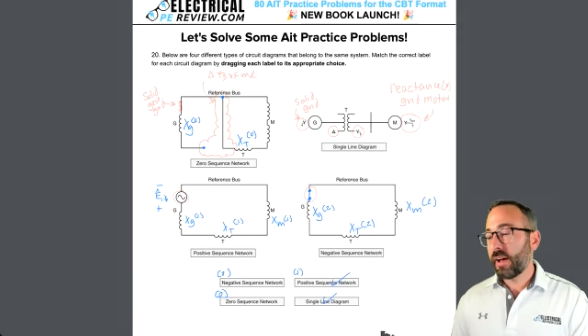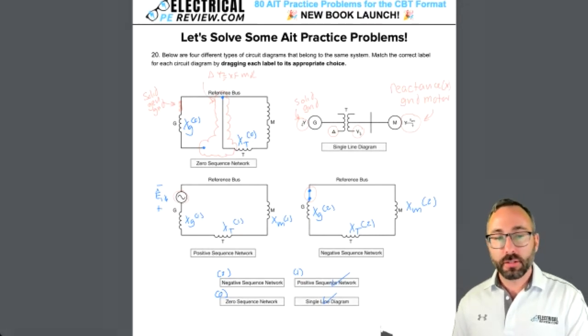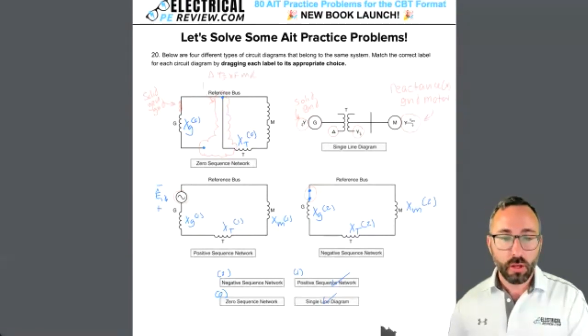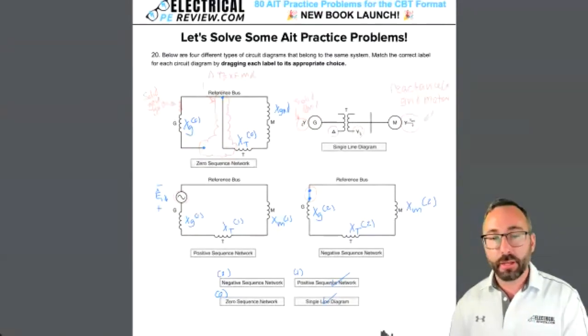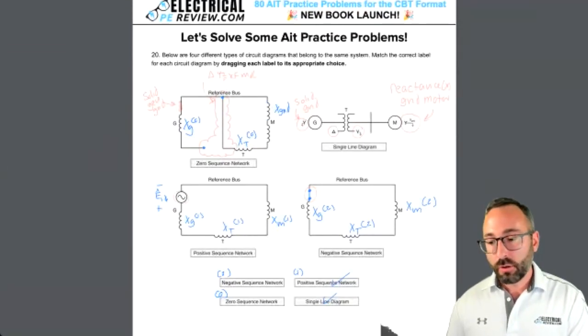What happens if I have a ground impedance or a ground reactance? What happens on the zero sequence network? I'm going to take that value X ground, whatever the reactance is right here, but I have to multiply it by something before I stick it on my zero sequence network. Anyone know? Yeah, multiply it by 3.